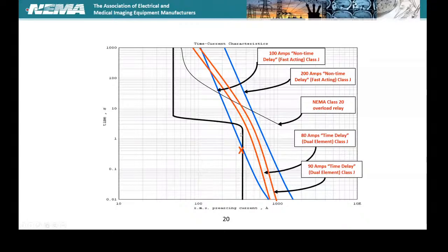We've got 4 separate fuses on our diagram. Now this fuse here, where we see there's an intersection in the line, that is a 100 amp non-time delay fuse, a class J fuse, non-time delay, fast acting. You'll see where they intersect right there. That means the fuse just blew.